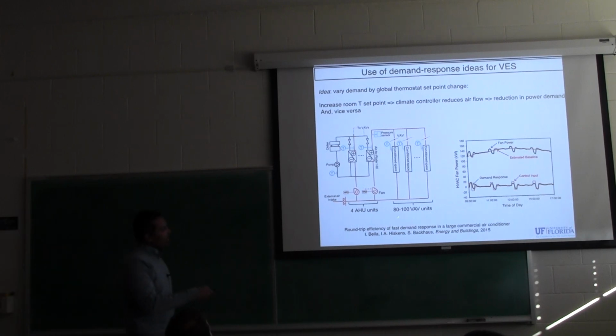The idea was that if you change the set points - suppose you increase the room temperature set point in all the rooms of the building - increasing room temperature means reducing the airflow, because that air is cold. So if airflow goes down in the entire building, the fan has to slow down. That's how you reduce airflow. The fan slows down, power consumption decreases, and vice versa.